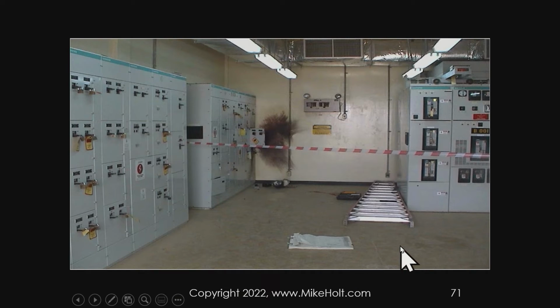Also, looking at this slide, we don't have time to get into this and this isn't the place, but it's the configuration of the wires and the buses, the way things are inside enclosures and the size of the box. If you're in front of a box, it isn't like you're in an open room and this thing goes out in 360 degrees, or a whole sphere - no, this thing is hitting something and you can see it, you can actually see a jet. It just happened to work out that way. And that jet could have gone down, or it could have hit the face. Here are some real pictures of somebody standing there.